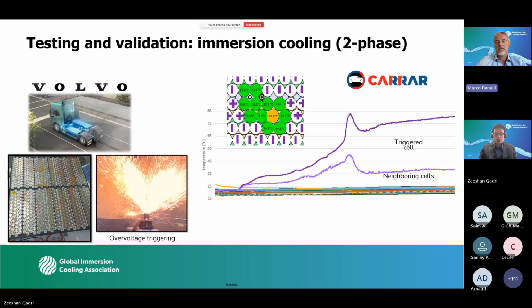But when the cell was triggered within the module using two-phase immersion cooling, actually the cell itself didn't exceed temperatures of around 85 degrees C. You can see this in the upper curve, while all the neighboring cells never exceeded 45 degrees C. So the very fast heat extraction, which happens with immersion cooling, using in addition phase change to the gas phase, introduced a tremendous increase in safety of the system. And I think this is the key message for today. This is the last technical slide on this point.